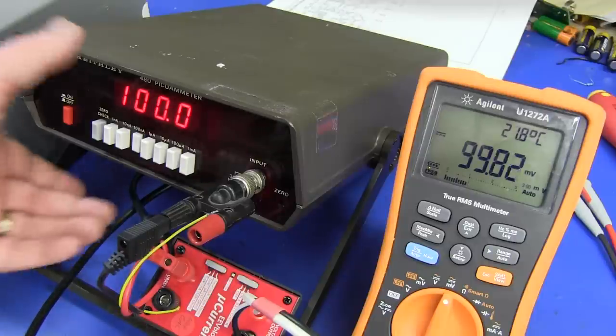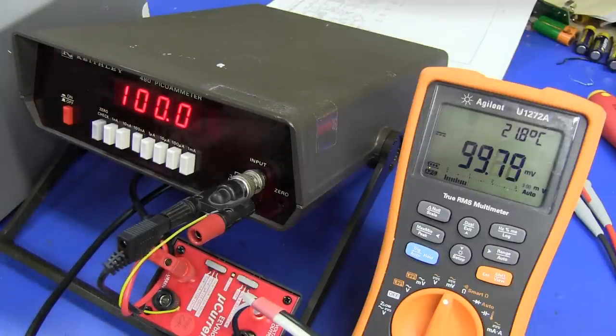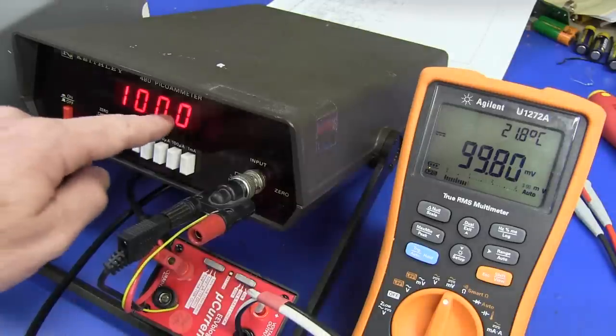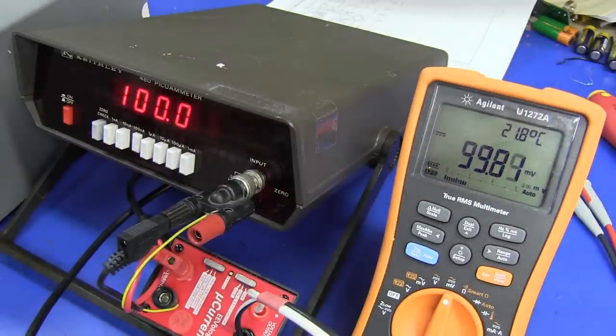And there it is, measuring in the order of 100 nanoamps there. And it might be two least significant digits out on here, but I'm not actually feeding in 100. I'm feeding in 99.9 microamps. So, you know, in theory, if everything's absolutely bang on perfect, this should be 99.9 nanoamps there, or 99.9 millivolts, because it's 1 millivolt per nanoamp range on my microcurrent. So there you go. Everything's well within spec.